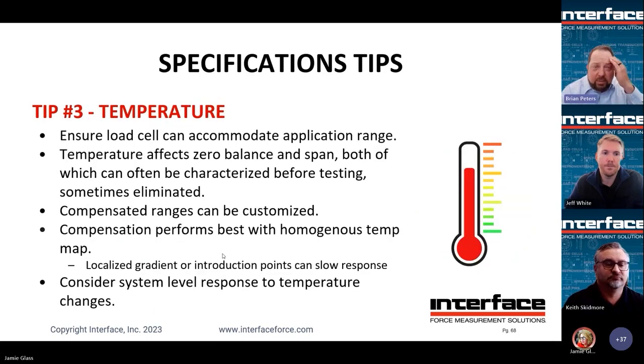Temperature. We've touched on this a few times, come back again. Key takeaways there are to understand how it affects both zero and span. It's characterizable. You can probably compensate some of that out of your test or remove some of it. We want to make sure any temperature is as homogeneous or consistent as possible around that sensor. And then again, think about the rest of your system. If you can run your whole system up to temperature to see how it responds with no force, that would be ideal. Every single mechanical thread, any mechanical joint, is going to respond differently to temperature. So even if you zoom in too much on the sensor, you may have other error influence that makes the sensor almost irrelevant. Next one.